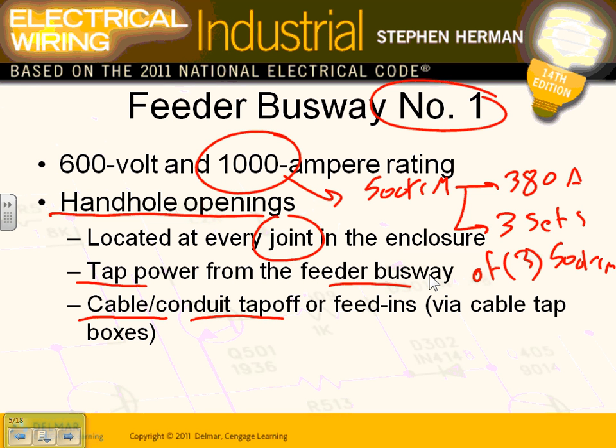For example, if I have a feeder right here, can I bring a conduit to a junction box inside the feeder and take a 225 amp feeder to a panel here? No problem. You have to have an overcurrent protection device. No problem. Any questions, guys, about the feeders?